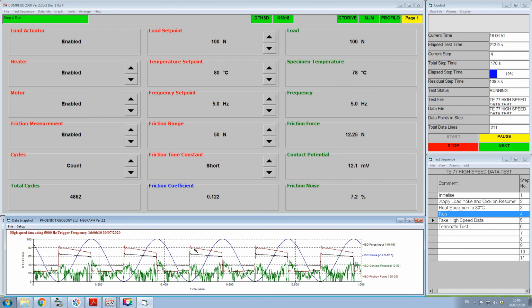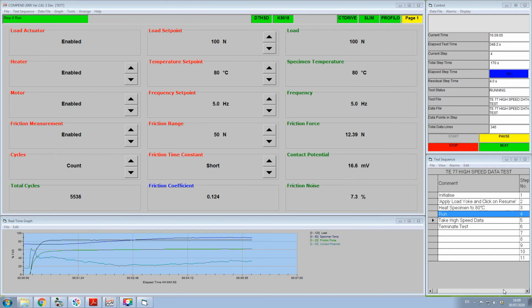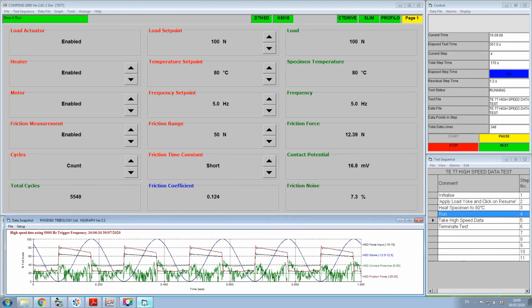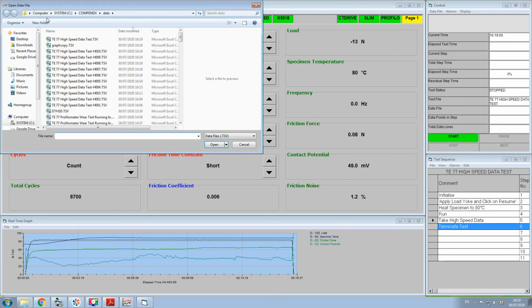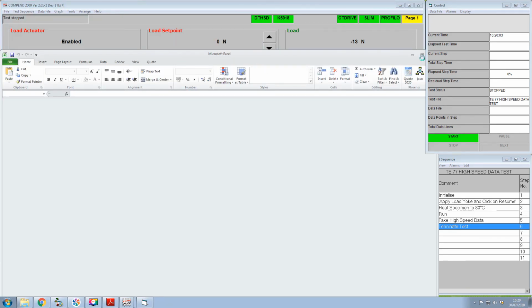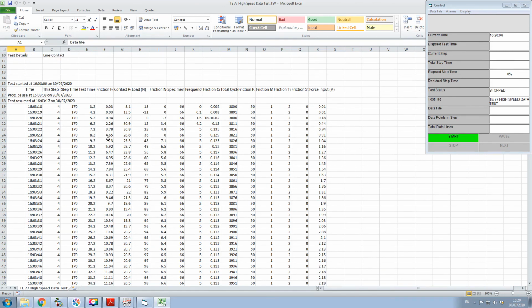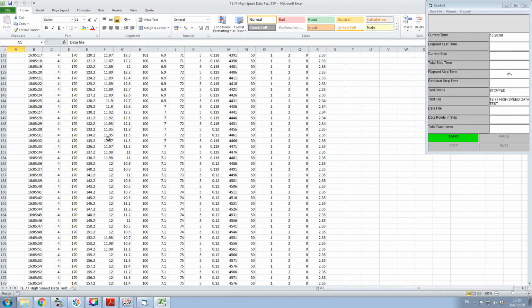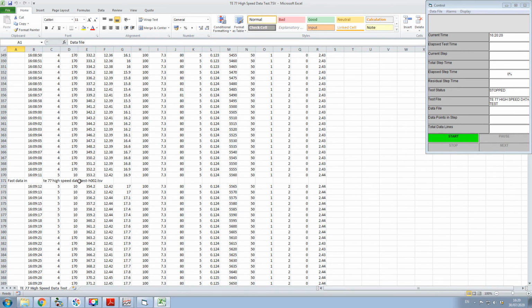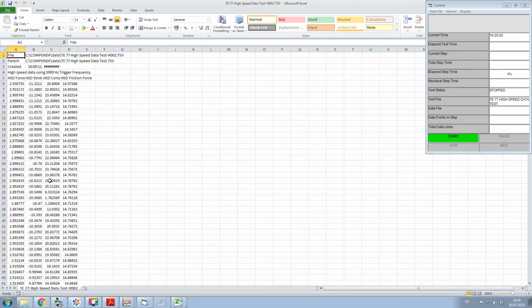Every time high-speed data is generated, a new data file is created and an entry made at the relevant point in the low-speed data file. At the end of the test, we can open the low-speed data file and scroll down to each high-speed data file. Automatically generated hyperlinks are provided for accessing the high-speed files directly from the low-speed data. Alternatively, individual high-speed files can be opened in the COMPEND data directory.